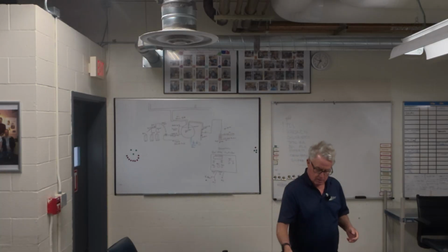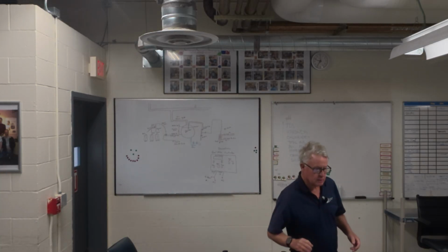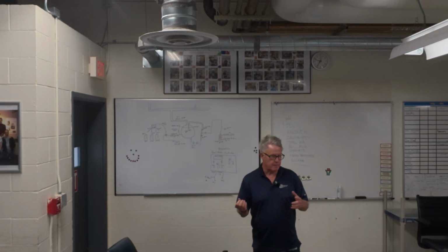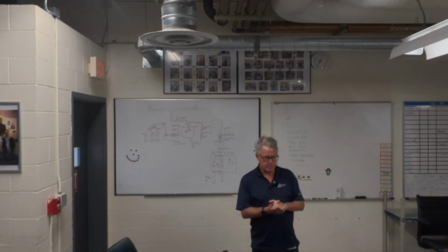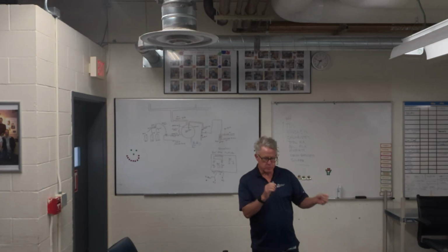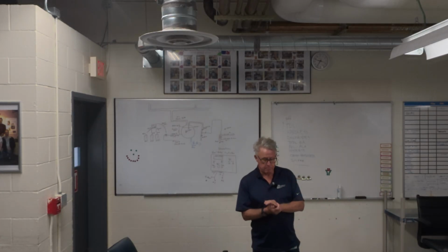The other major problem is sulfite control. We add sulfites to the water to capture available oxygen in the water. Oxygen can pit the boilers. So those are the main two targets—most boilers we hear fail, not ours, but because they got pitted or developed scale and needed an acid wash.